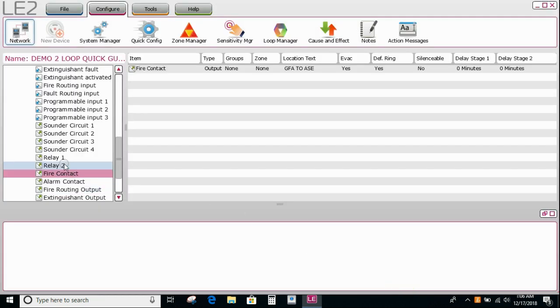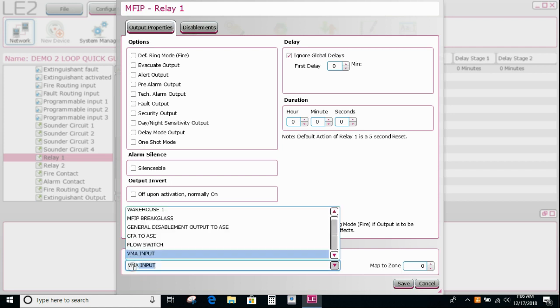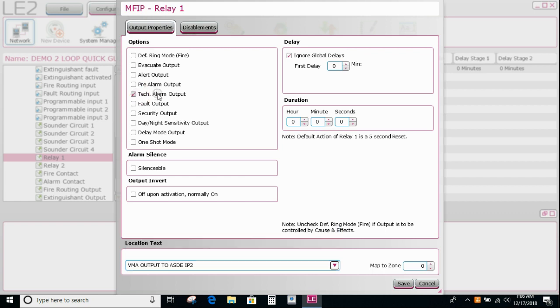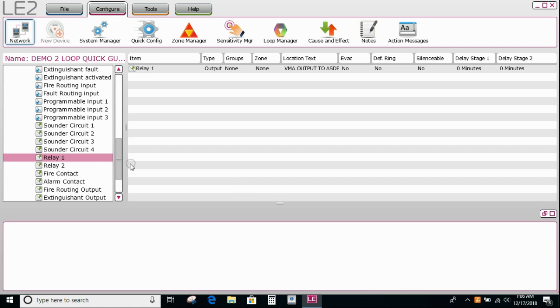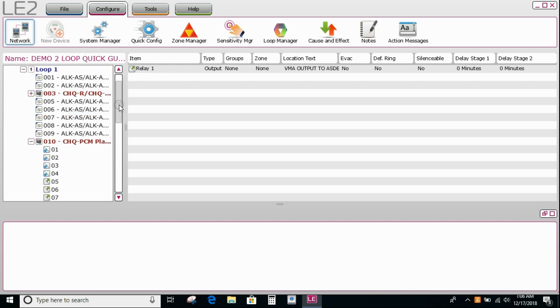So if we then look at the, let's say, relay number one, which we're going to now program to be VMA output to ASDE IP2. So in this case we're going to use this. If the VMA input was checked as a tech alarm, so if I tick that box there, it means that this output will be operated by any input that's got the tech alarm selected.